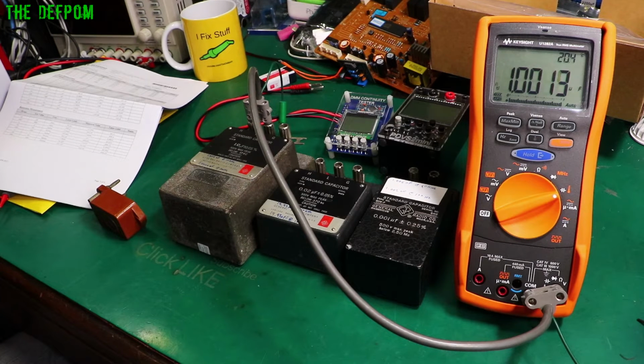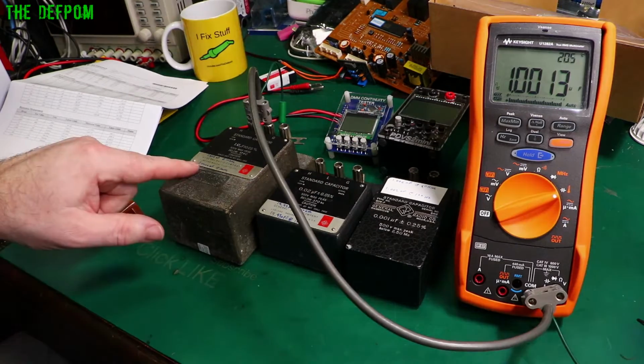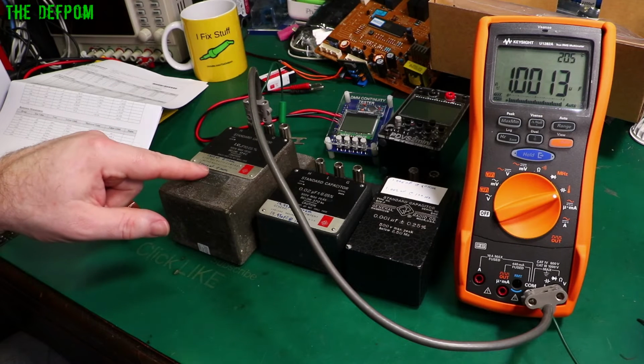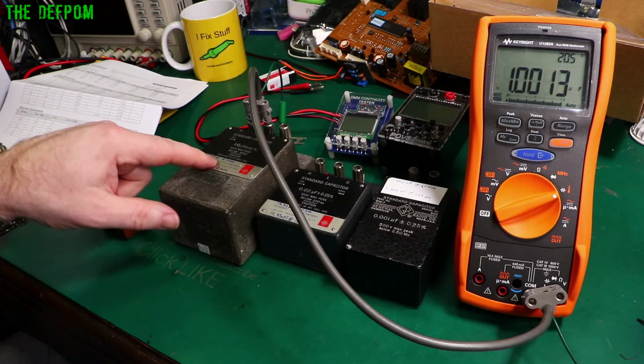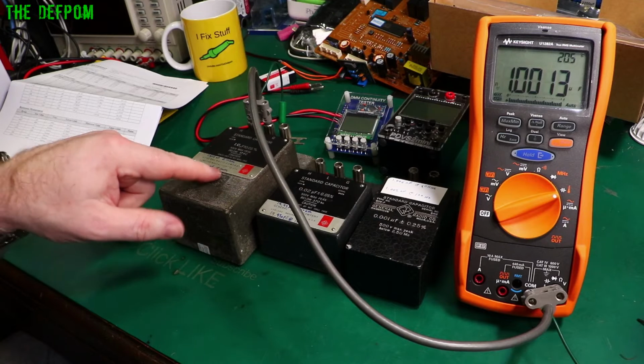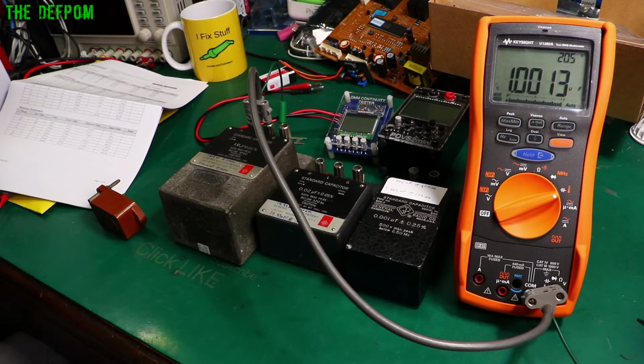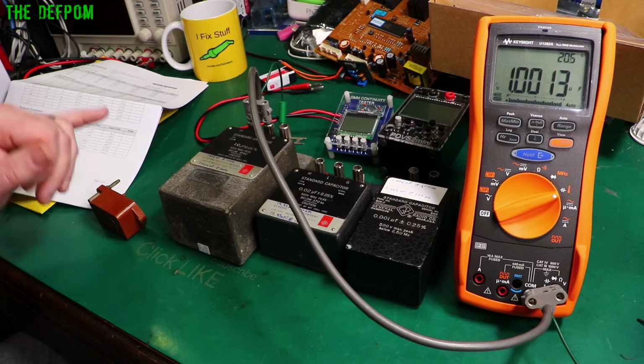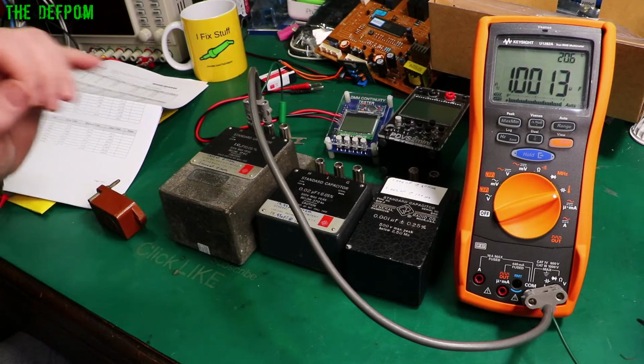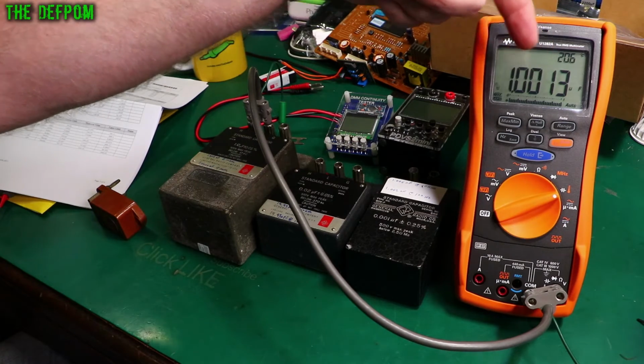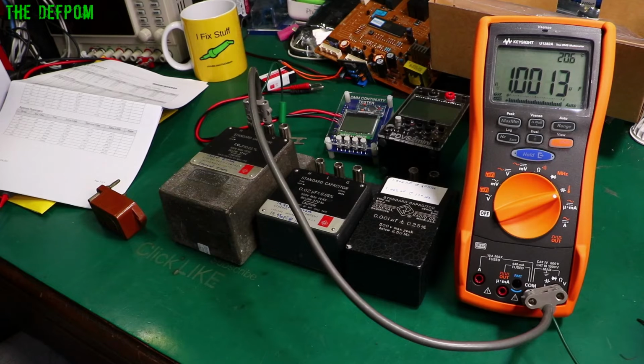It's the 1 microfarad. 1.001, that's looking pretty good. And according to the calibration, 1.0001 is what it's giving it during calibration, so again that's an order of magnitude out compared to what the calibration data is. My own measurements have done confirmations of basically what these are, but yeah, 1.005 at 10 kilohertz and exactly 1 microfarad at 100 hertz. So I suppose it depends on what this frequency is as well. But to put this in perspective, the upper limit for the spec is 1.01. So it's another order of magnitude higher than this. So that's actually pretty good.